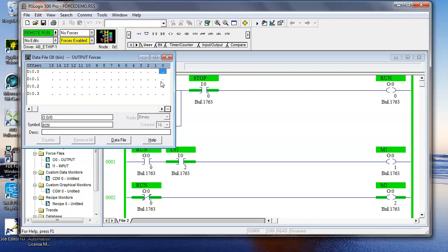Yeah, so forcing is built into all these PLCs. Now, basically, you have to build a force table. So you can only force the contacts that you put in that table, but you still are going to take away the control of all the safety systems built into that system.